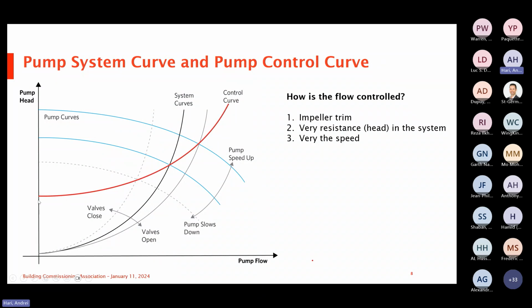And what's important here is that the way the control curve is determined is that, first of all, you will have your design point, which is when all valves are open, and then you will have your minimum system pressure at 0 flow. And what's important about understanding this point here is that this point is determined by where the DP sensor is located in your system. And we're going to cover that in a bit more detail in the next few slides. But the point being here is that understanding how the control curve is determined and how it is set up in a system is paramount into understanding, first of all, variable speed pumping, and then how sensorless control works.